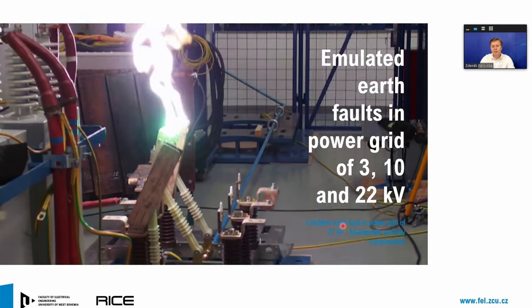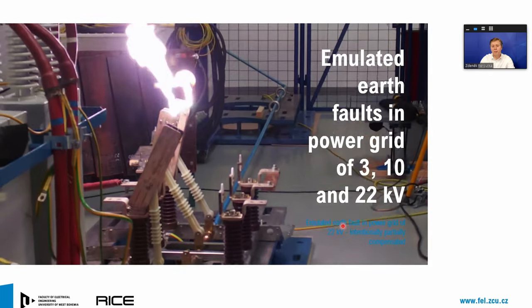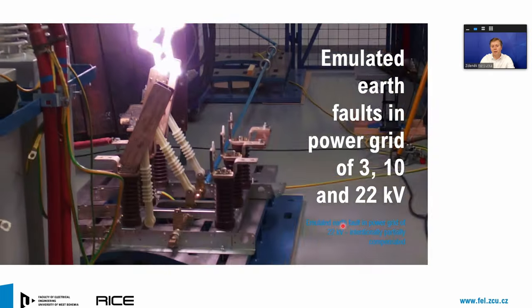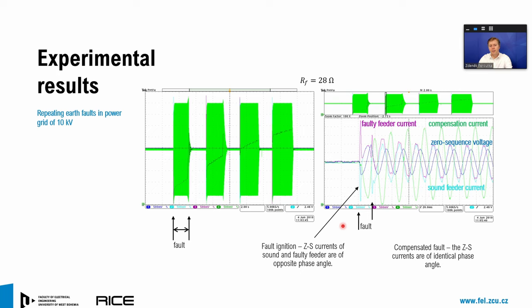Here you can see how dangerous a non-compensated earth fault can be. This is a video which shows what can happen in the system if you do not properly compensate the ground fault current. Just to illustrate how fast our compensation can be, here you see the generation of the compensation current. Here you see the current of the faulty feeder. Here you see the current of the sound feeder. The fault is compensated when the currents are of identical phase angle, which you can see occurs very fast. So we are able to compensate the ground fault in below 20 milliseconds.